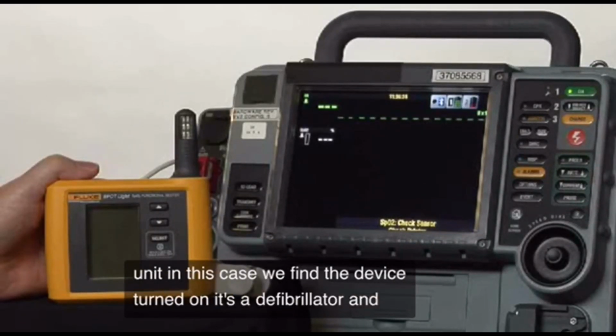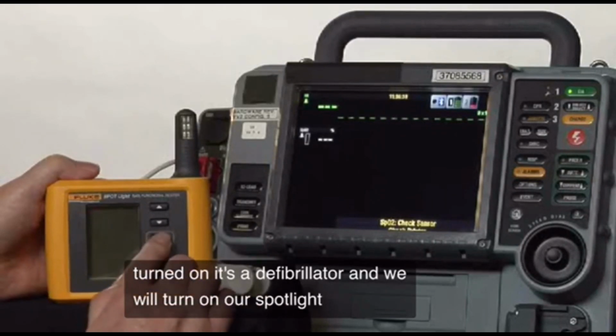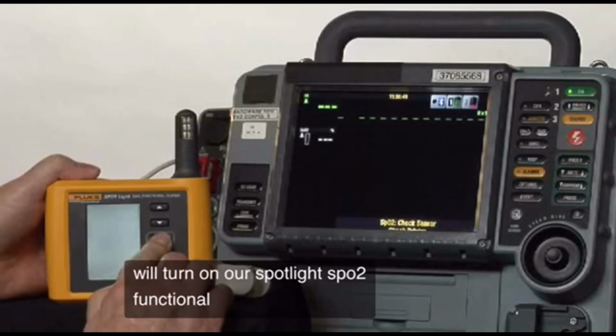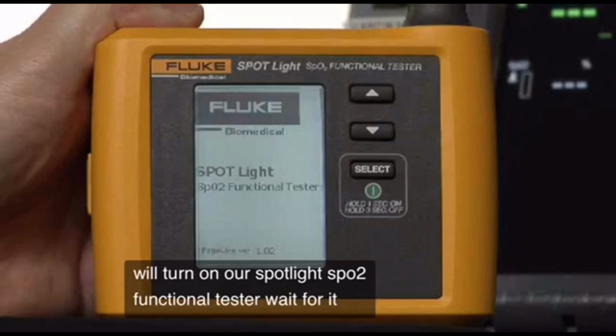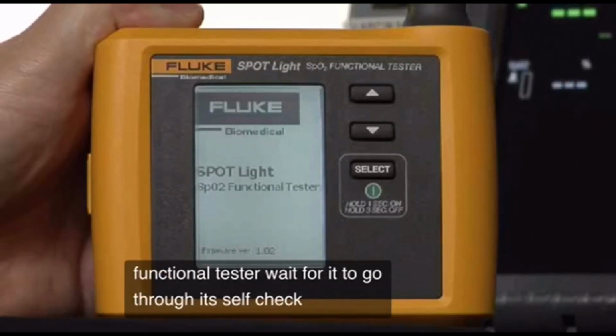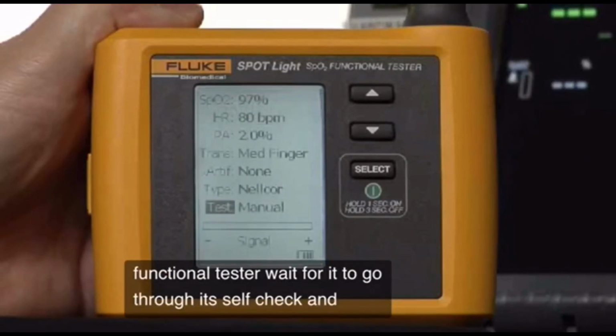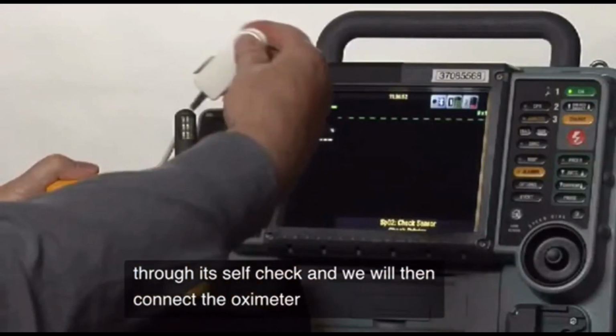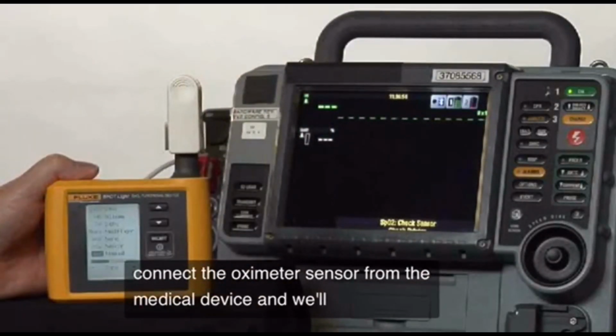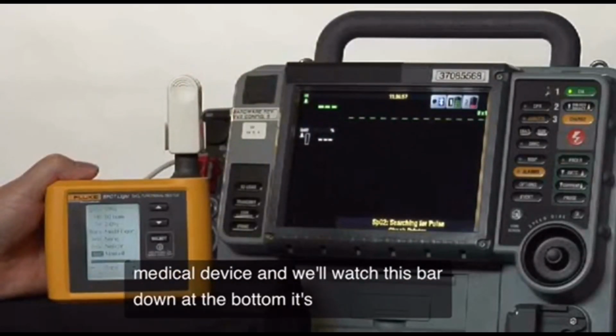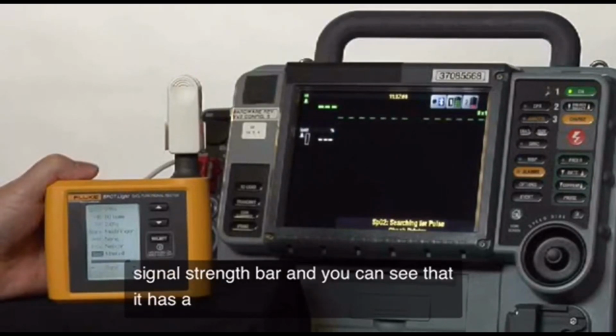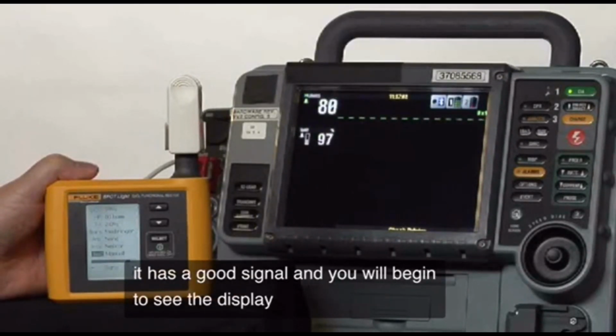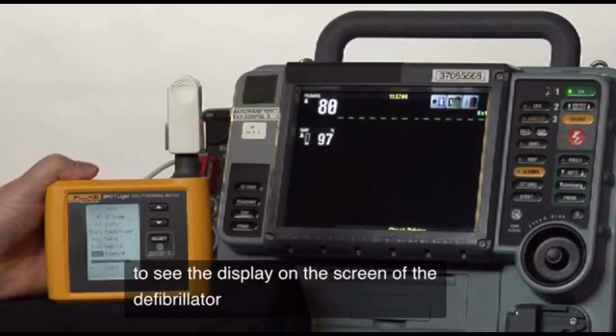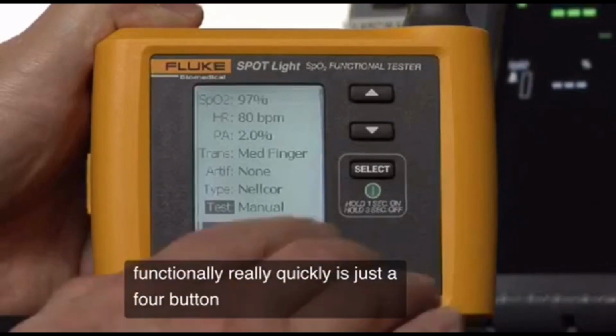It's a defibrillator. And we will turn on our Spotlight SpO2 functional tester, wait for it to go through its self-check, and we will then connect the oximeter sensor from the medical device, and we'll watch this bar down at the bottom. It's called the signal strength bar, and you can see that it has a good signal, and you will begin to see the display on the screen of the defibrillator. Now, testing this functionally really quickly is just a 4-button push.